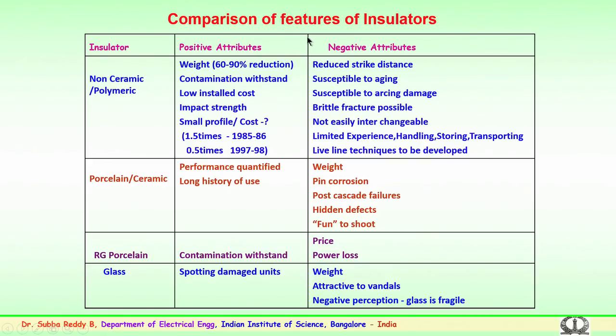So, when you compare these four, you see both the positive and the negative advantages. In the positive, we have better weight reduction, depending upon the voltage level; the insulator string weight comes down by up to 90%. This is a very important factor for the utility people. Being lightweight, it is very easy to string and advantageous.